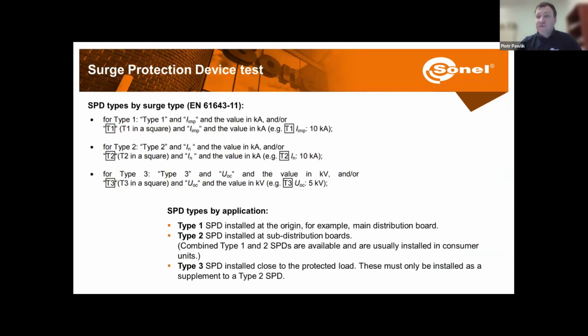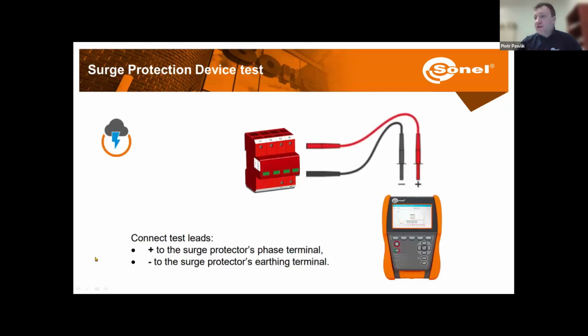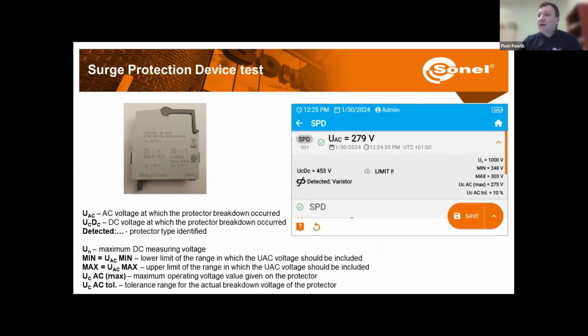So we have different types of the SPDs. Now, as per here DC vehicle chargers, we are going to use the type 2. So they are treated, the chargers, similarly as sub-distribution boards. Now we are going to connect the meter plus test lead to the phase terminal, minus test lead to the earth terminal, and we are going to start the test. So we can check the AC voltage at which the protector breakdown is going to occur. And also we can check this with the DC voltage.